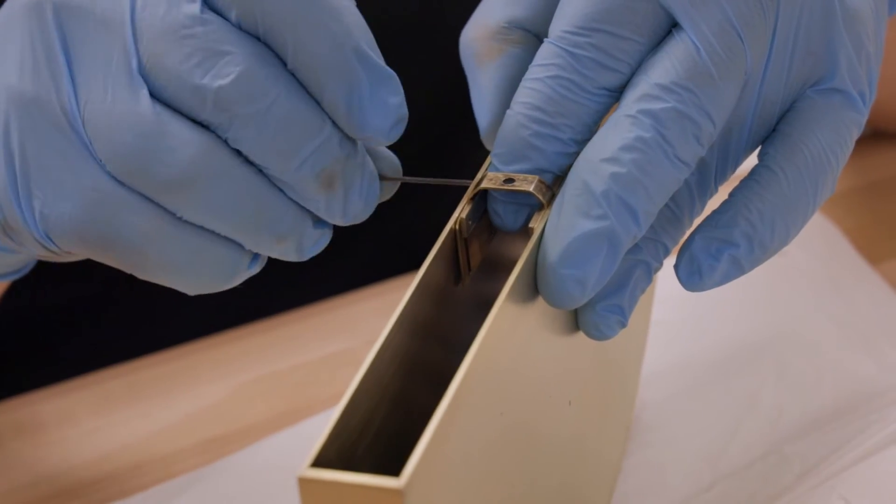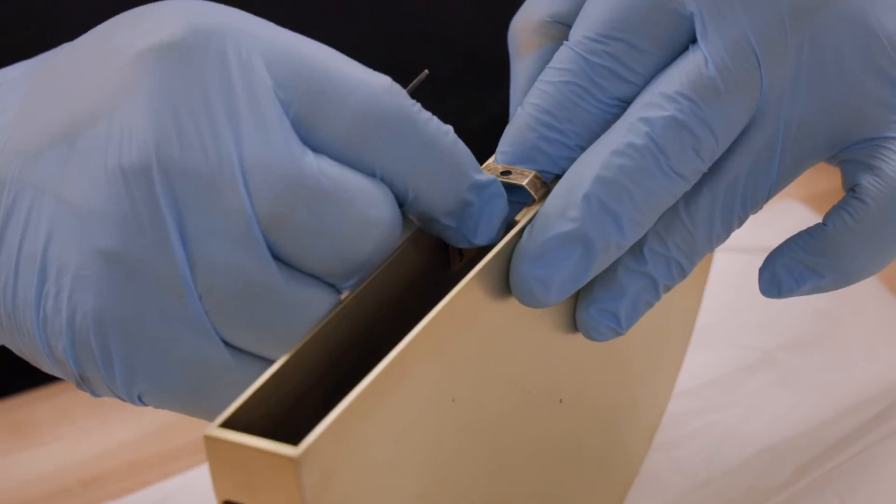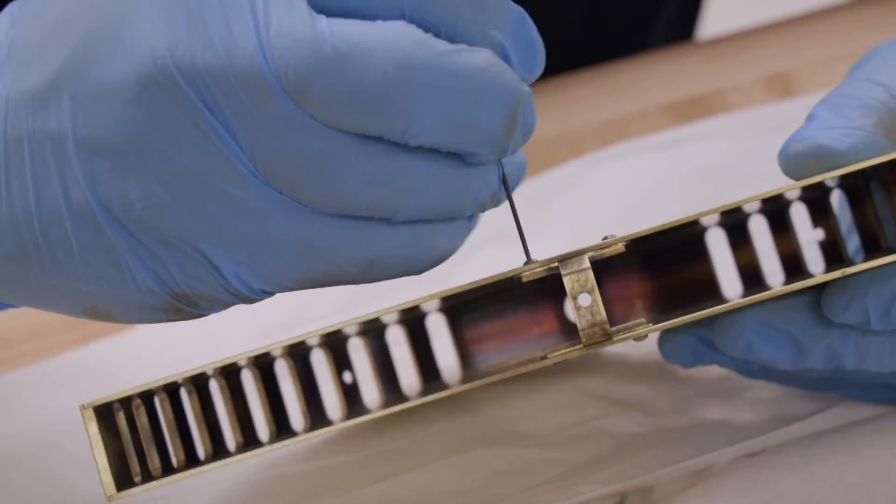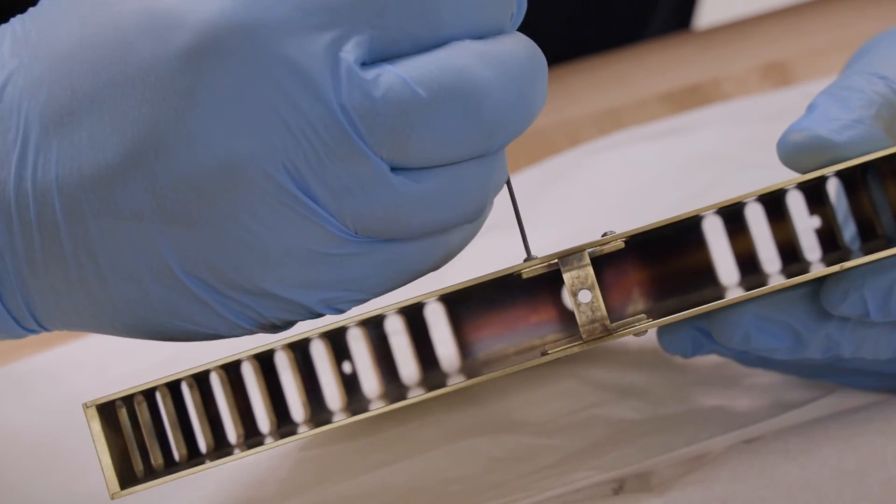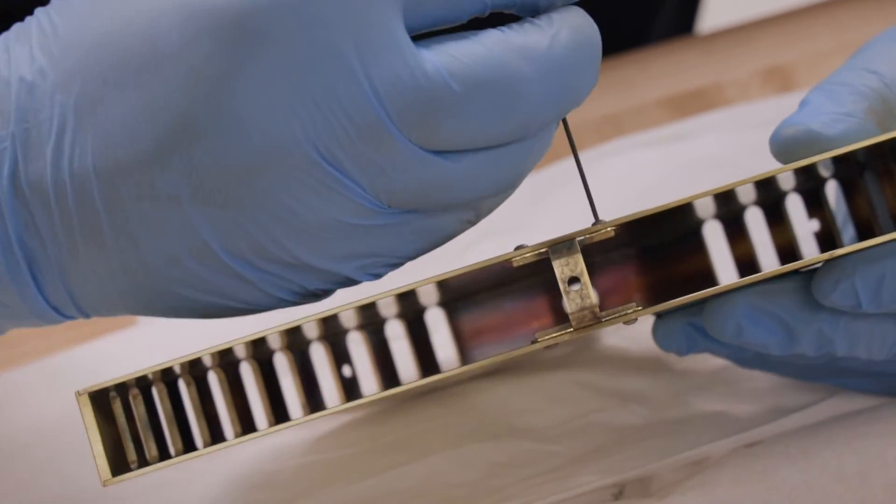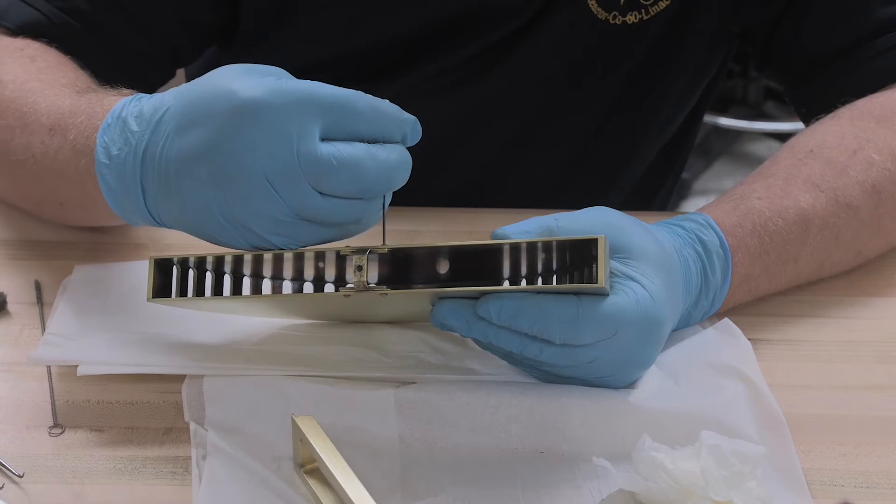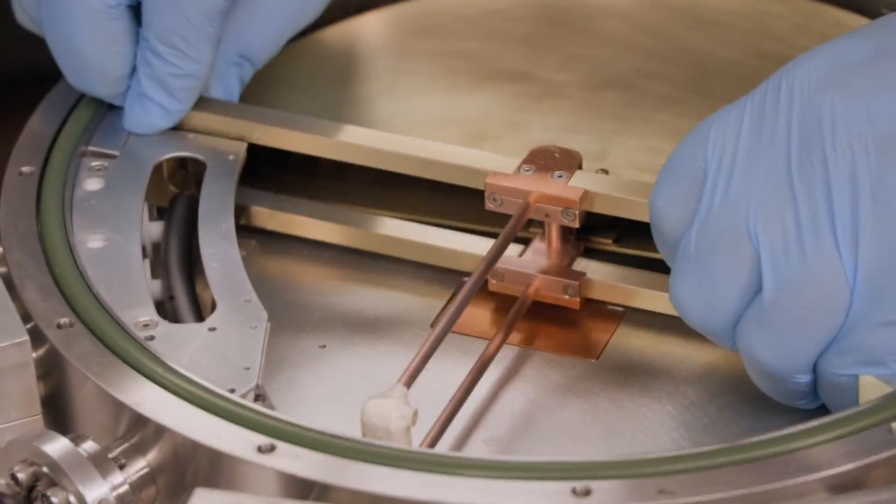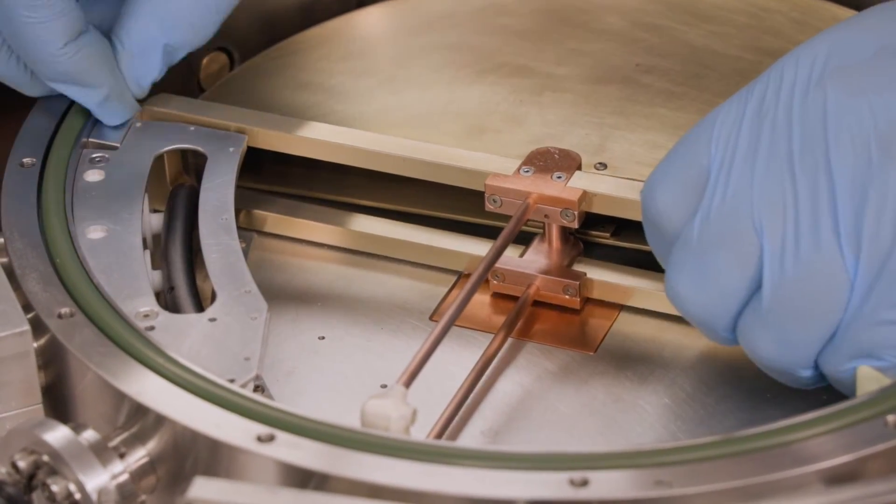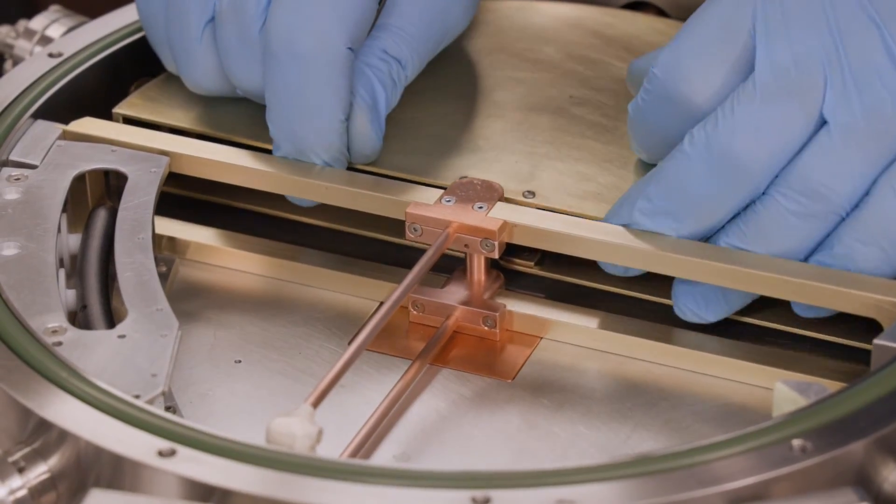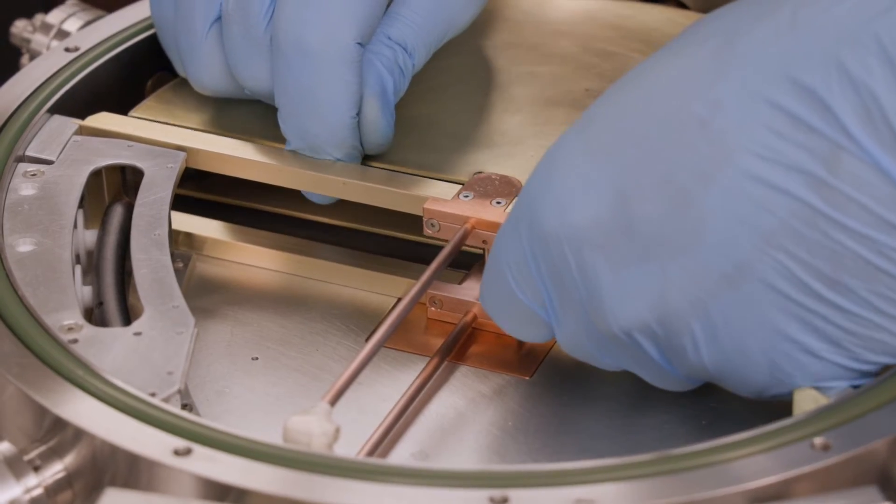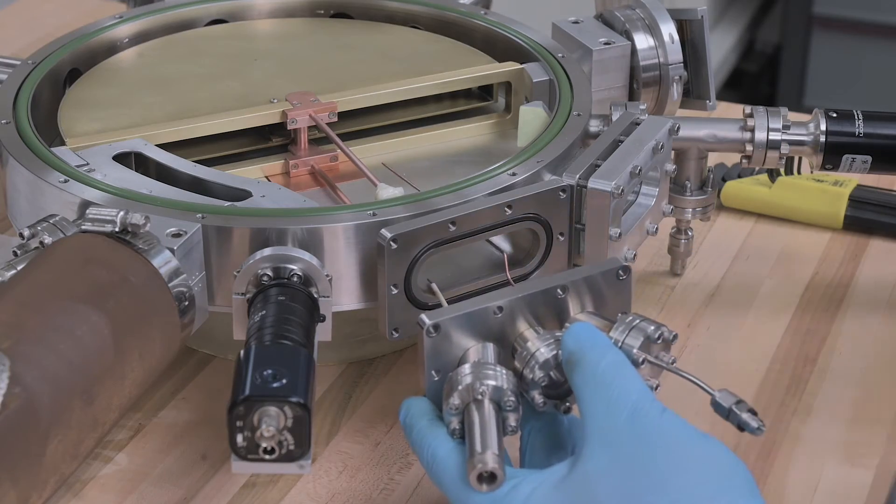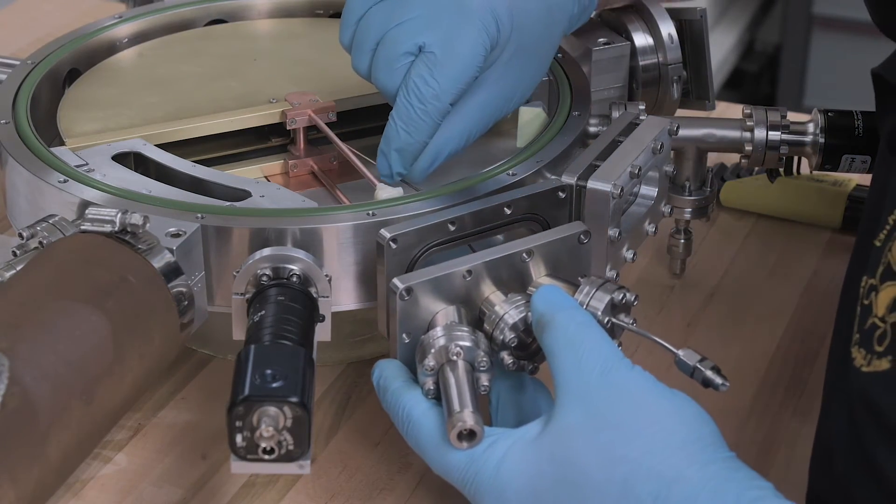After cleaning the d, we install the extraction electrodes, also known as pullers. Note that this puller has a circular aperture. The d is reinserted, followed by the dummy d ion source assembly. Then I adjust the d's position to align the puller with the ion source. We return the service flange and connect the high voltage lead and reinsert the gas delivery line.